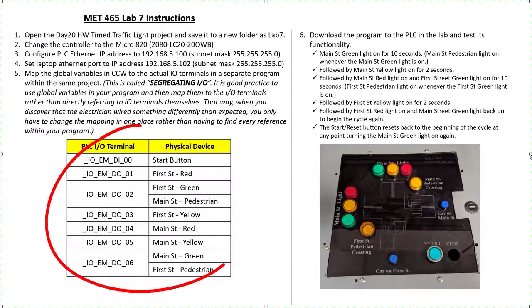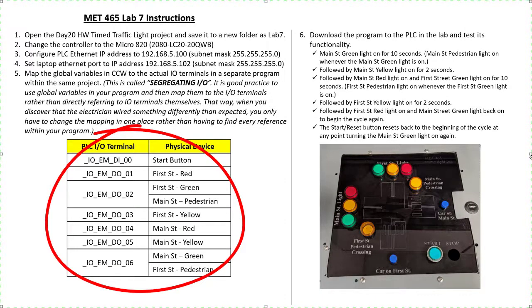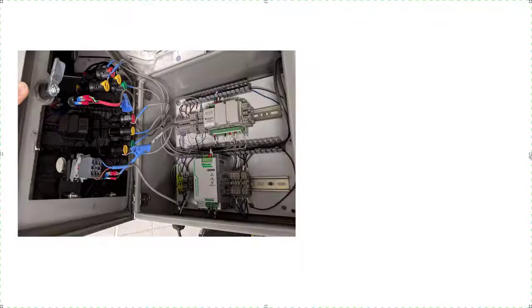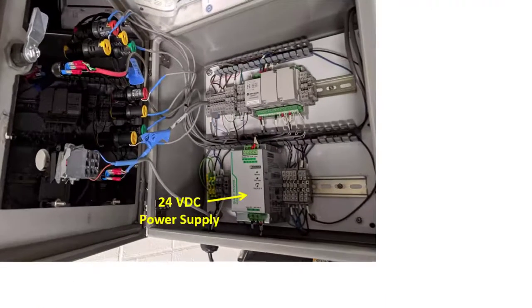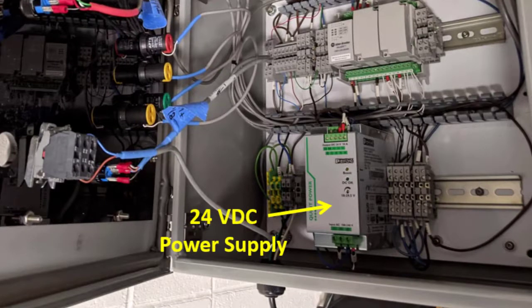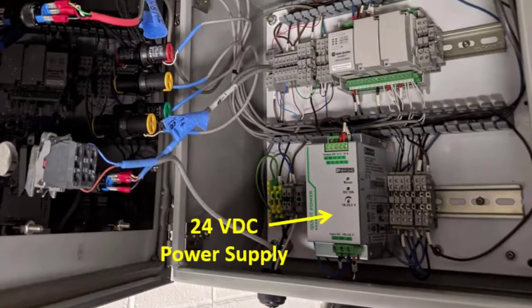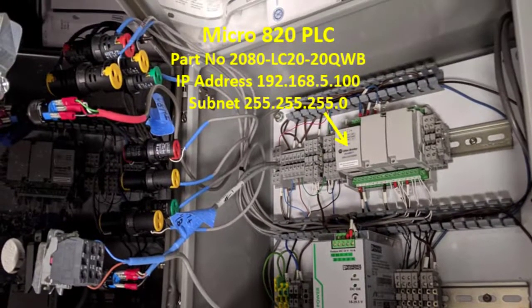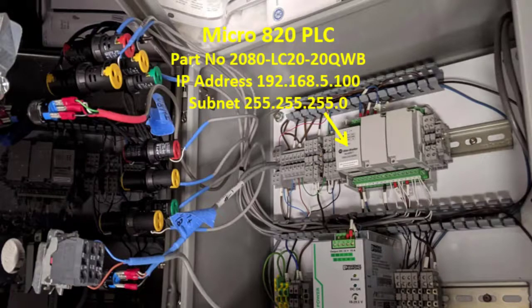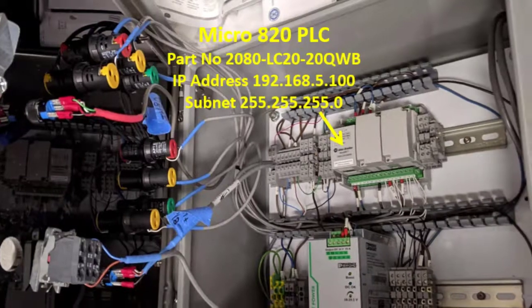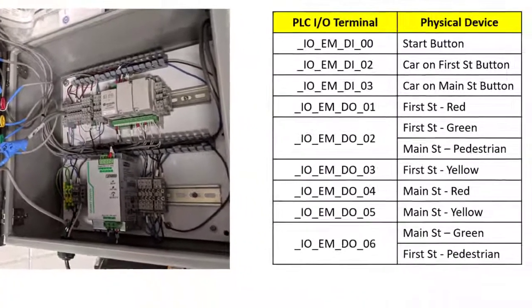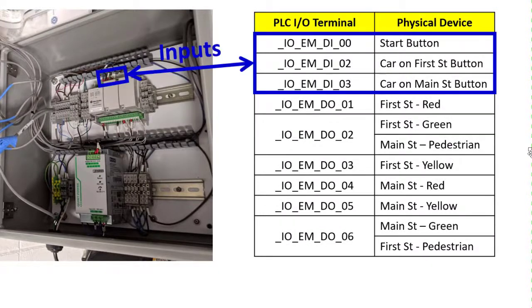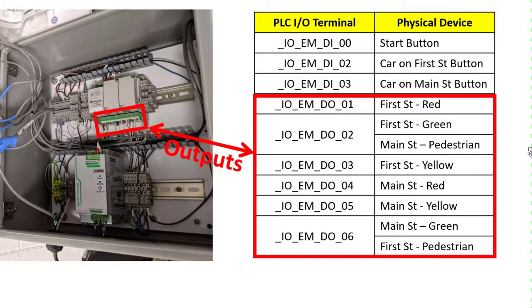You can see here how the physical devices have been actually wired to the I/O terminals on the PLC. And one of the main objectives of this lab is to help you see how and why we segregate I/O. This is a photo inside the electrical cabinet. If you remember, there's a 24 volt DC power supply that takes 120 volts from the wall outlet and converts it to 24 volt DC to supply power to the rest of the system. This is our Micro 820 PLC. You can see the part number as well as the IP address that's set for that PLC. And here's how the input and output terminals have been wired to the physical devices.